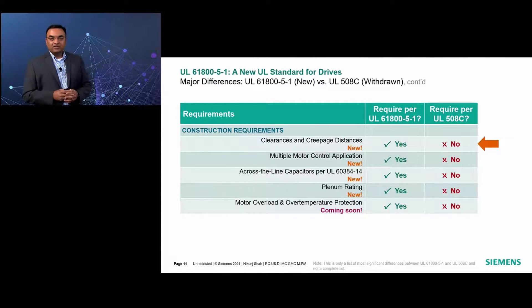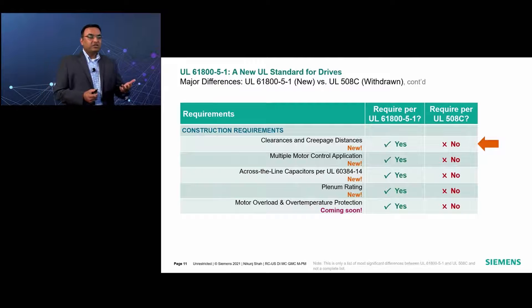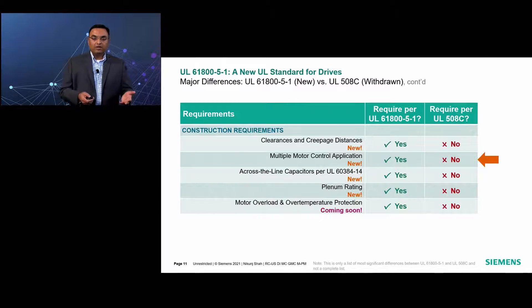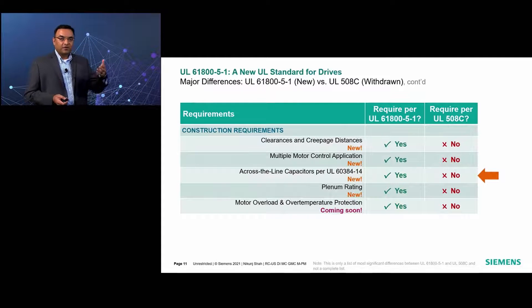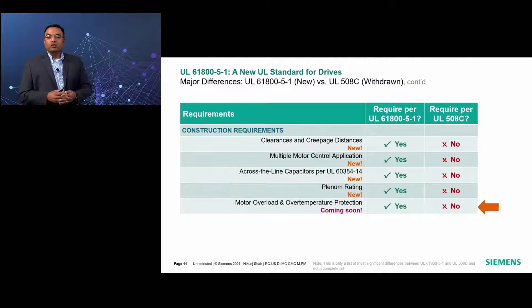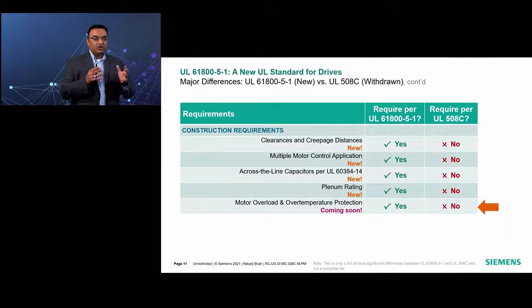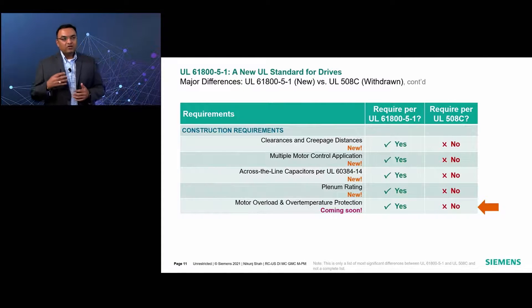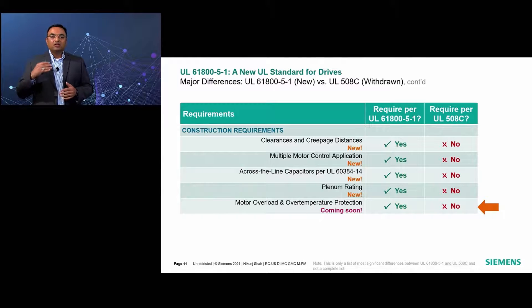As you can see, in addition to the clearance and creepage distance requirement, there are more demanding design requirements that the drive needs to comply with in the new standard 61800-5-1 as compared to the old UL508C. The important ones include, for example, multi-motor control applications to control multiple motors using a single drive, across-the-line capacitors for AC filter or DC bus capacitors, plenum rating requirements, and new revised motor overload and over-temperature protection requirements. All these requirements have been added newly into this new standard which were absent from the old UL508C, again showing that drives certified according to this new standard have a higher level of product safety.